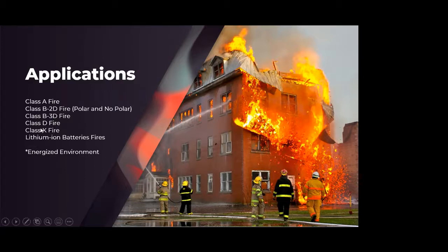It also works on Class D fires. Remember what our droplet looks like — it looks like that orange. We've changed the substance on the surface, so when an F500 encapsulator agent droplet comes onto a Class D fire, we don't have H2O coming into contact with the high-burning-temperature metal. This removes the separation of hydrogen and oxygen that causes explosions. This opens a whole new avenue for fire protection engineers and for NFPA. We're currently working with the Minnesota Fire Marshal on a project to educate them on what this droplet looks like and why you can use an encapsulator agent on Class D fires, but not plain water.